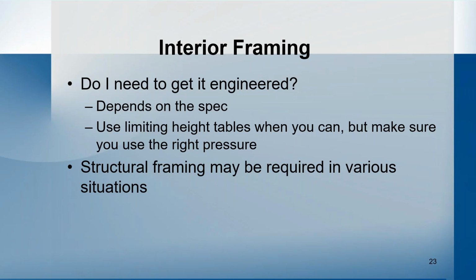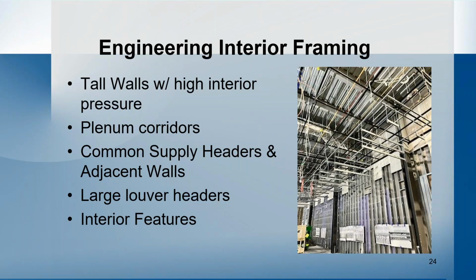So when you're looking at interior framing in a data center, you a lot of times get outside the realm of when you're allowed to use non-structural framing and when you're forced to use structural. So when does it need to be engineered? If you have tall walls with a high interior pressure, there's plenum corridors. So it's areas where they're pumping air through that, again, have those higher pressures and sometimes some weird configurations to them. There's a number of data centers that use what's called common supply headers in their adjacent walls. So this is another area where they're pumping high pressured air through, and this is all part of the cooling process for the data centers to help keep them cool.